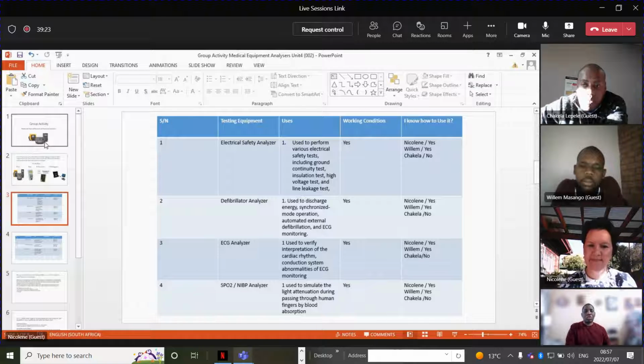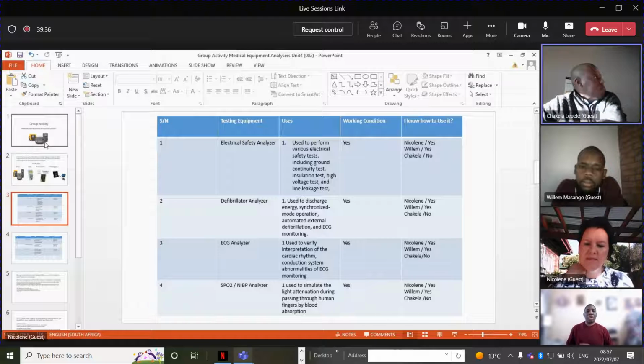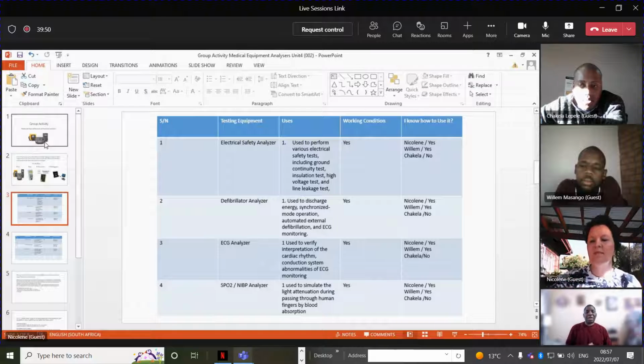With the SpO2 for oxygen saturation and NIBP, which is non-invasive blood pressure, yes, you are going to see the use of the ProSim 8 vital sign simulator. When we do patient monitoring, you do the theory, and then you see the patient monitor, and then you will see how all of these tests are done to measure all the parameters in the patient monitor. And that takes 2 days because it's quite a lot. So the theory, 1 day, the practical the next day. So there's quite a lot there. You will get to see how to use that. Next slide.